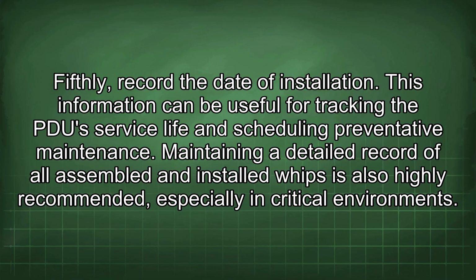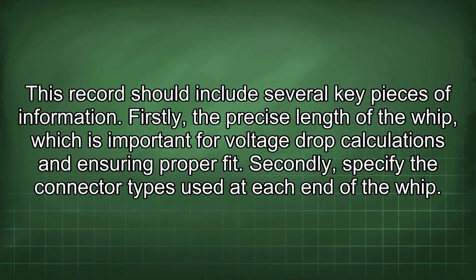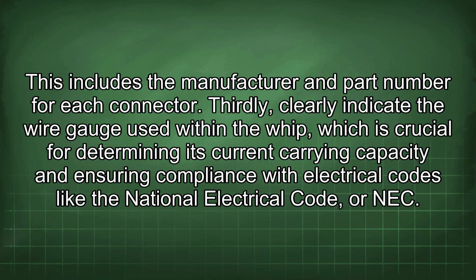Maintaining a detailed record of all assembled and installed whips is also highly recommended, especially in critical environments. This record should include several key pieces of information. Firstly, the precise length of the whip, which is important for voltage drop calculations and ensuring proper fit. Secondly, specify the connector types used at each end of the whip. This includes the manufacturer and part number for each connector.